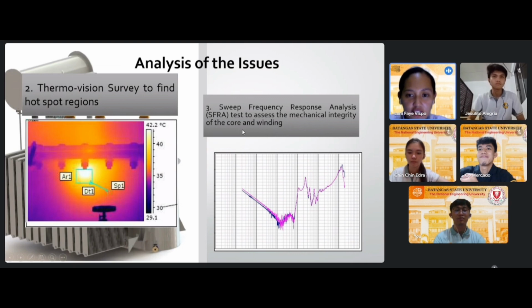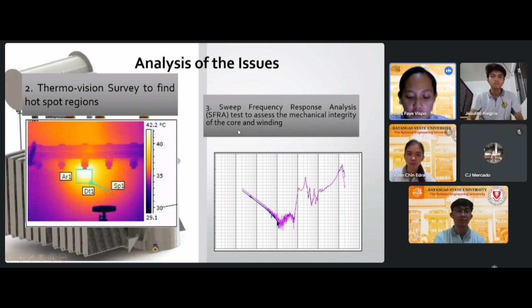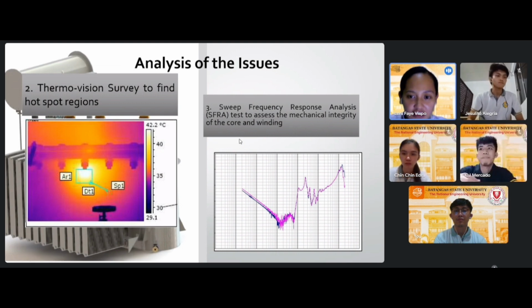The other one is the sweep frequency response analysis, or SFRA test, to assess the mechanical integrity of the core and winding. The SFRA test is a response analysis test performed offline to determine how the impedance of the test specimen behaves over a specified frequency range. It is also used to determine the physical condition of the transformer's active elements, and it aids in locating the source of the problem with the transformer.